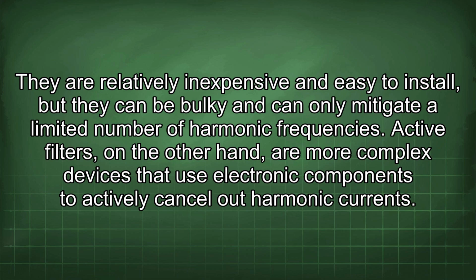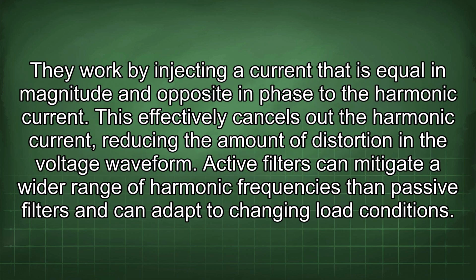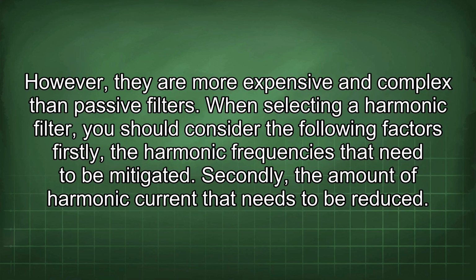They are relatively inexpensive and easy to install, but they can be bulky and can only mitigate a limited number of harmonic frequencies. Active filters, on the other hand, are more complex devices that use electronic components to actively cancel out harmonic currents. They work by injecting a current that is equal in magnitude and opposite in phase to the harmonic current. This effectively cancels out the harmonic current, reducing the amount of distortion in the voltage waveform. Active filters can mitigate a wider range of harmonic frequencies than passive filters and can adapt to changing load conditions. However, they are more expensive and complex than passive filters.